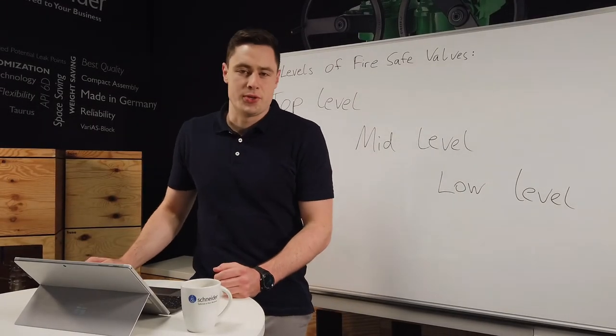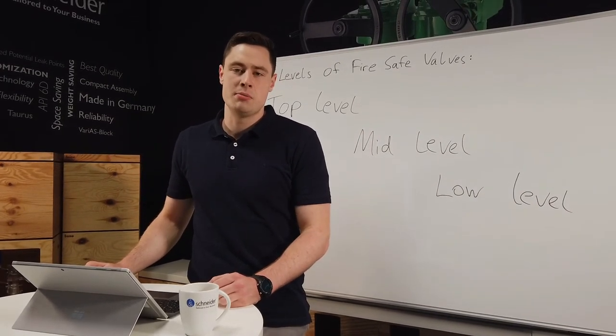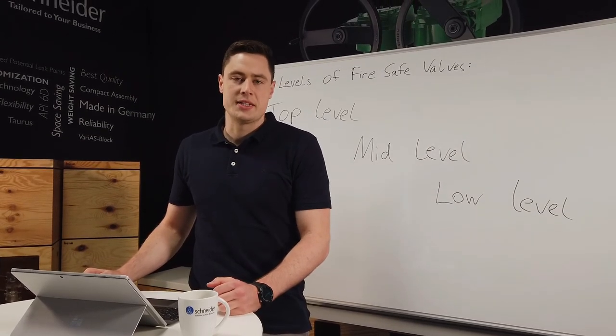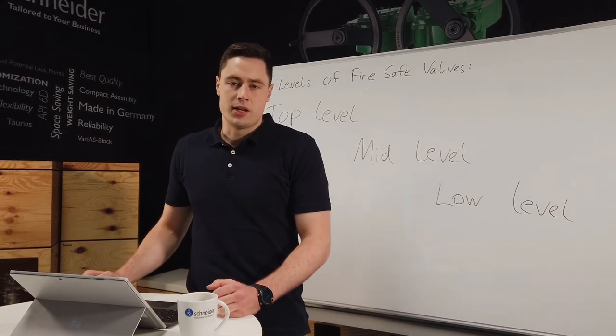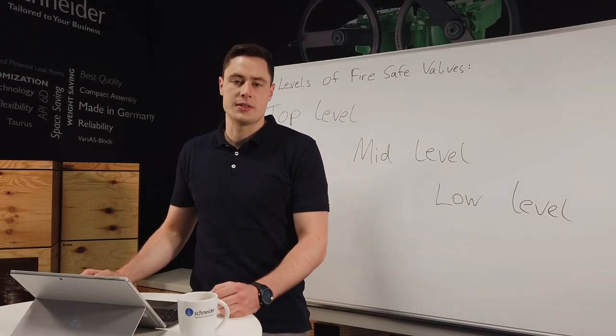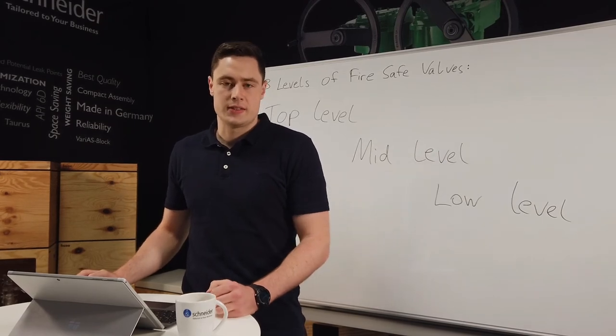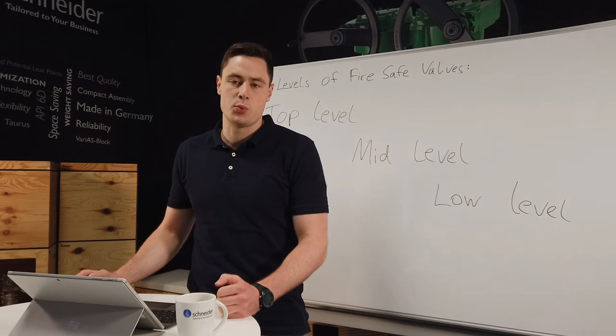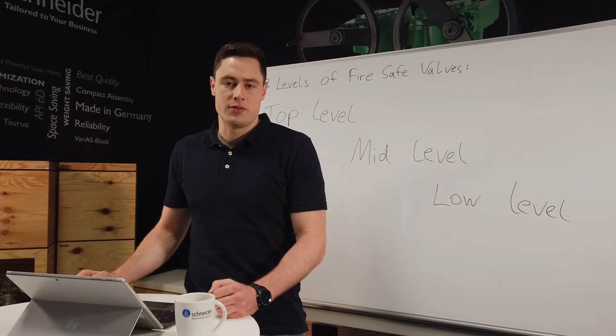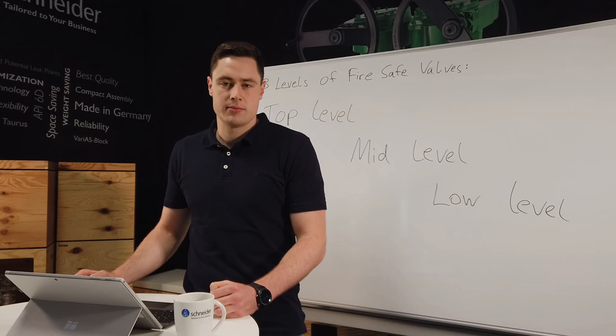Now let me share a personal experience with you. We had a terrible experience during a fire safe test of our DBB monoflanges, which consists of the valve body and three needle valves for isolating and venting the medium. Each valve we developed was tested extensively in our tech center to be sure that all requirements of our customers are met. And in the case of fire safe approval, we do pre-tests in our fire safe test rig before we order a third party for witnessing. For the monoflange approval, we were very confident that we would pass the test at the first trial because we only used metal-to-metal sealing and graphite packing.